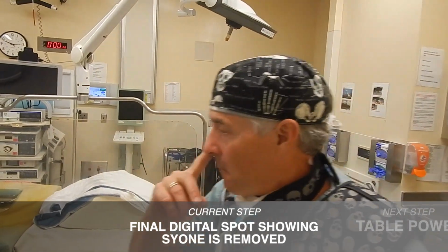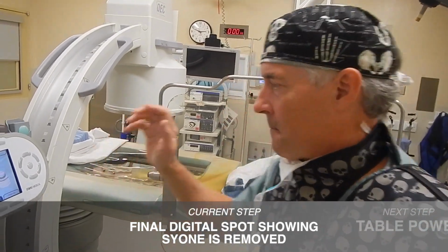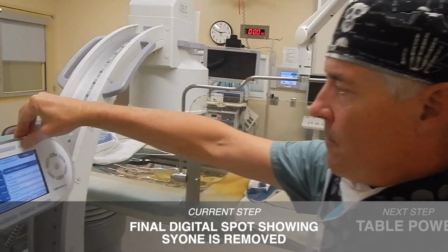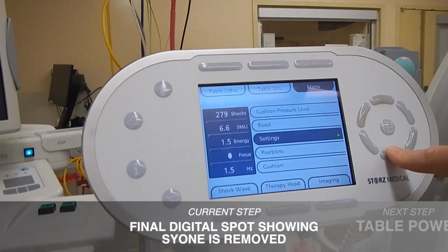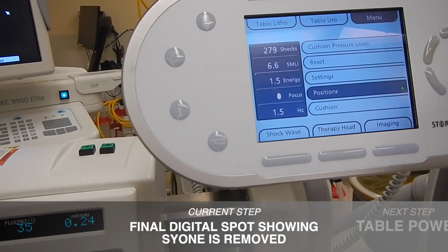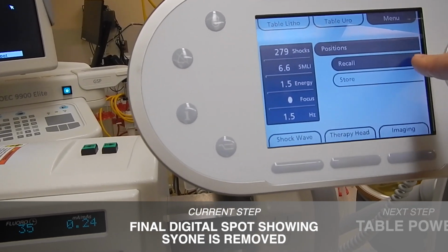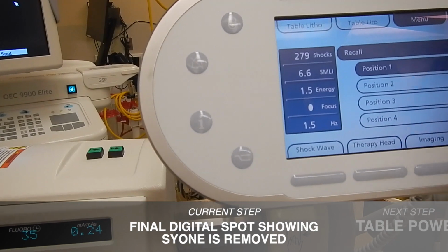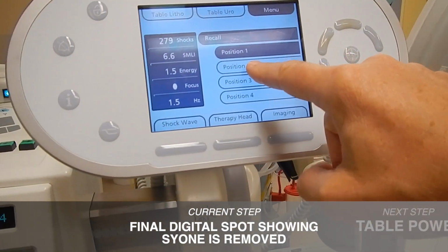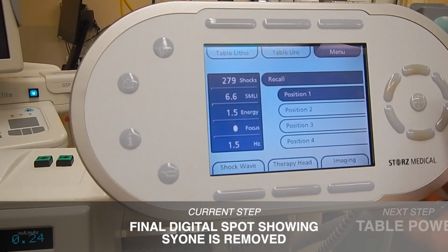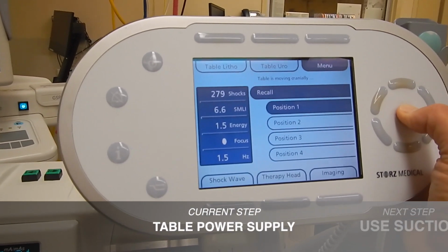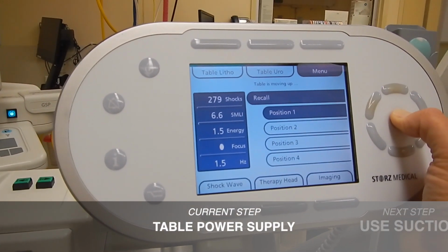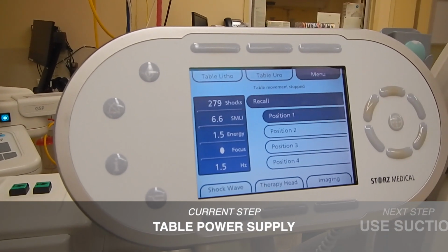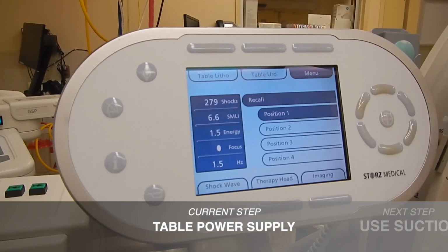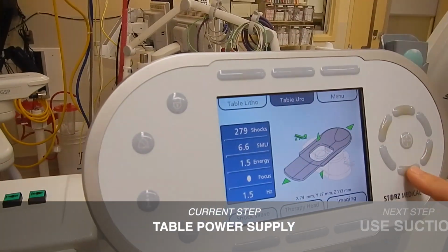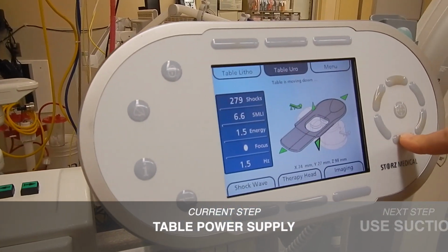Okay. So then, if we had another ESWL booked, what you want to do is go to menu and scroll to positions. And this is telling you that there's more to the menu, so you press that and you press that once more. And position 1 and 2 have been programmed to zero the table. So all you do is hold this down, and whatever movement you've done will return to center. If it starts to go up, you know you're centered. So then you just press Table Uro, and now you just go all the way down.